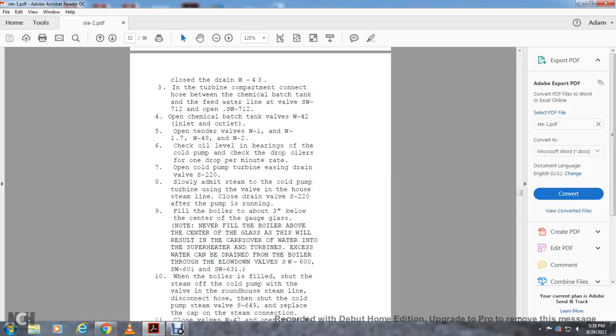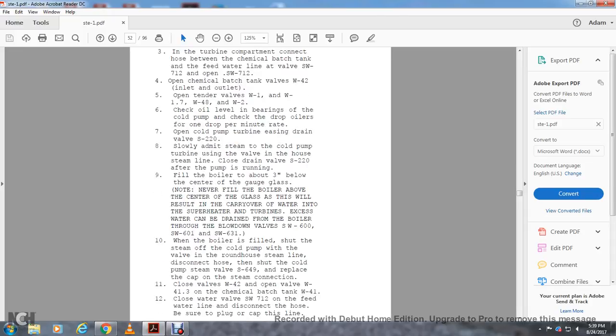Fill the boiler to about 3 inches below the center of the gauge glass. Never fill the boiler above the gauge glass, as this would result in carryover of water into the superheater and turbines. Excess water can be drained through the boiler blowdown valves SW-600, 601, and 631. When the boiler is filled, shut off the steam for the cold pump, using the steam valve on the roundhouse steam line, and disconnect the hose.